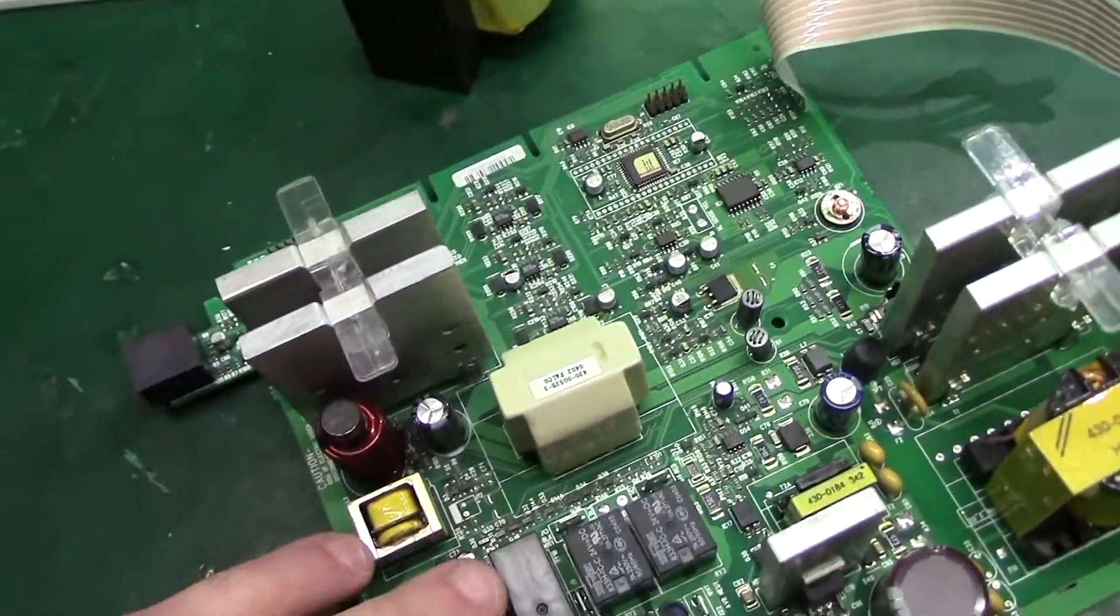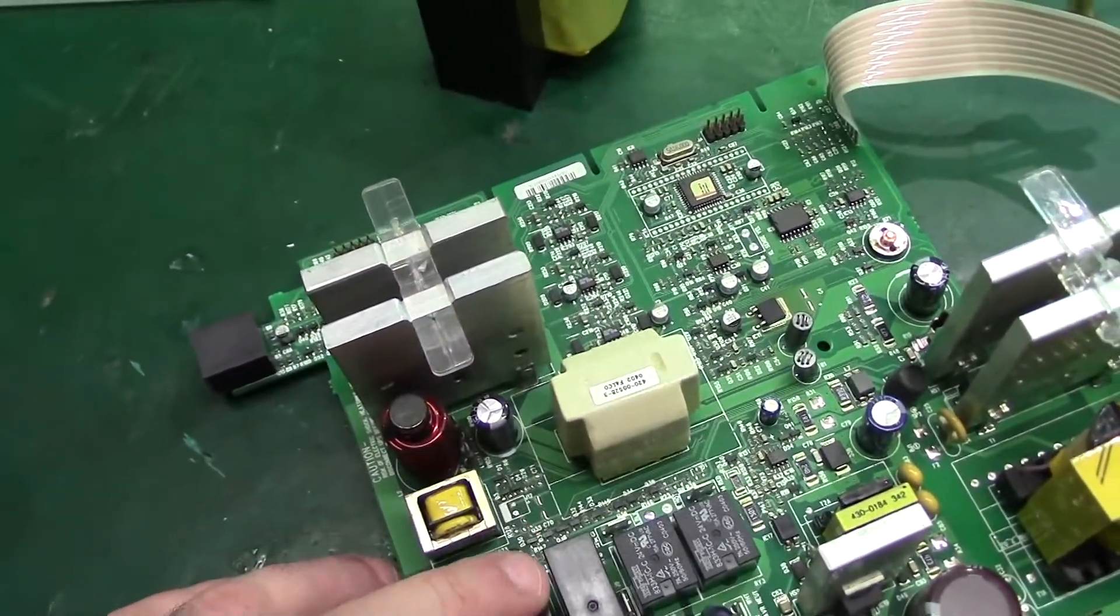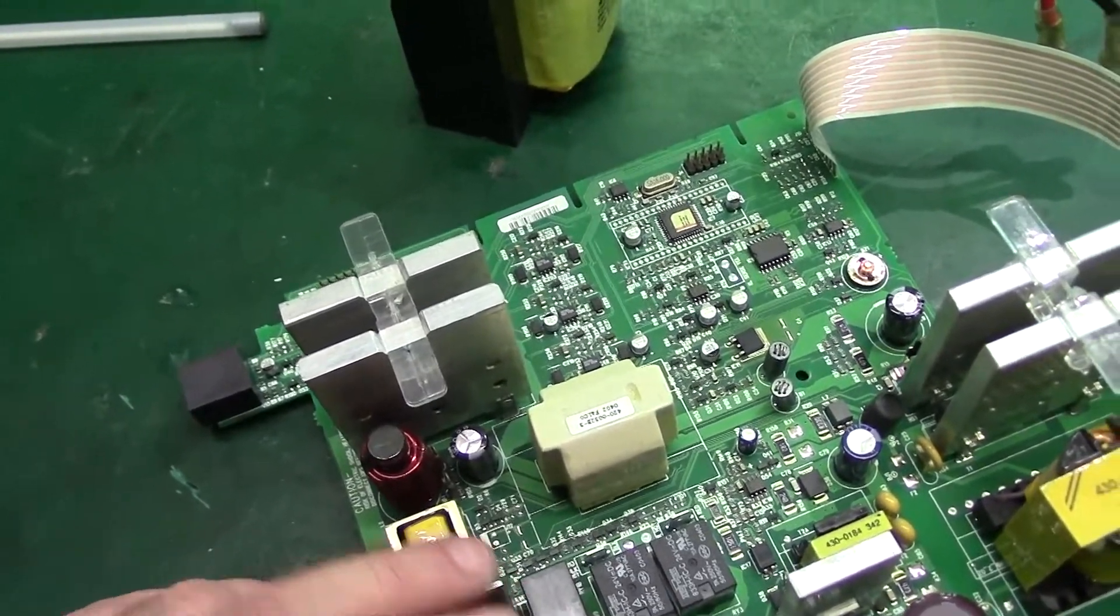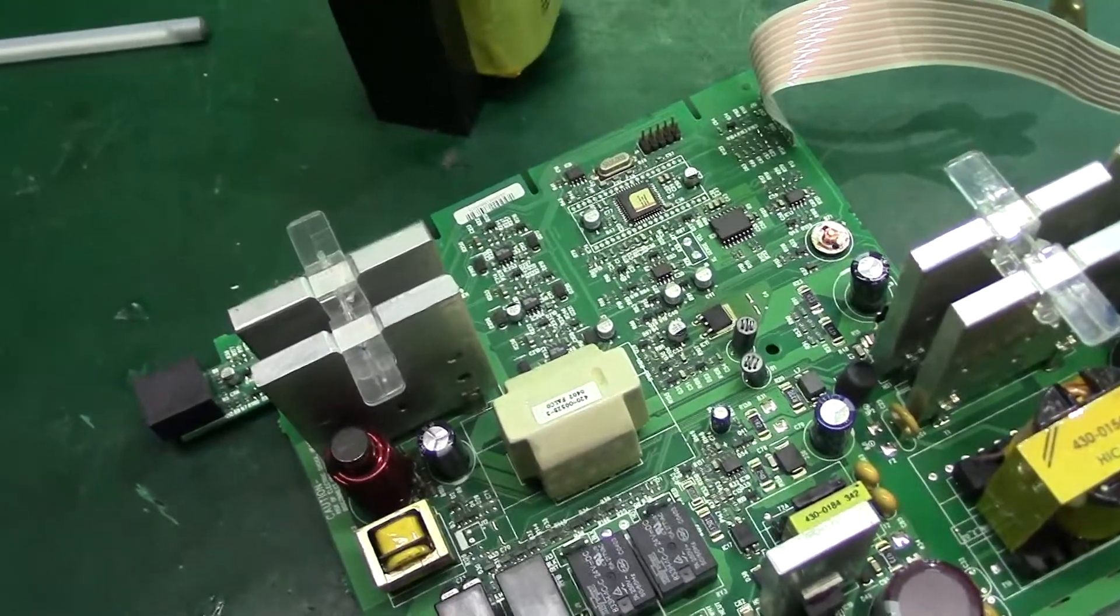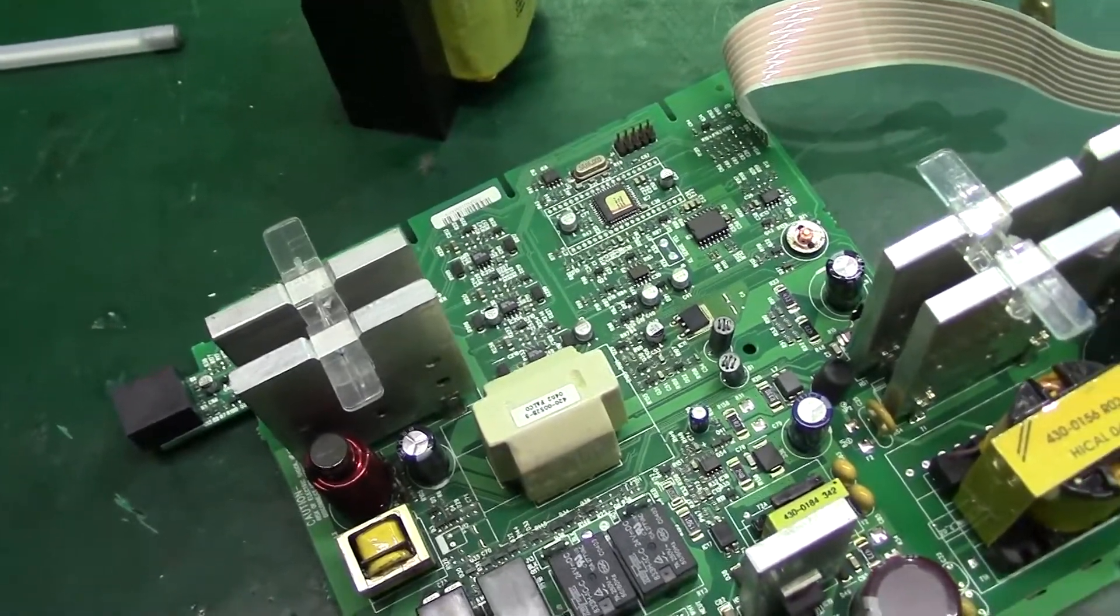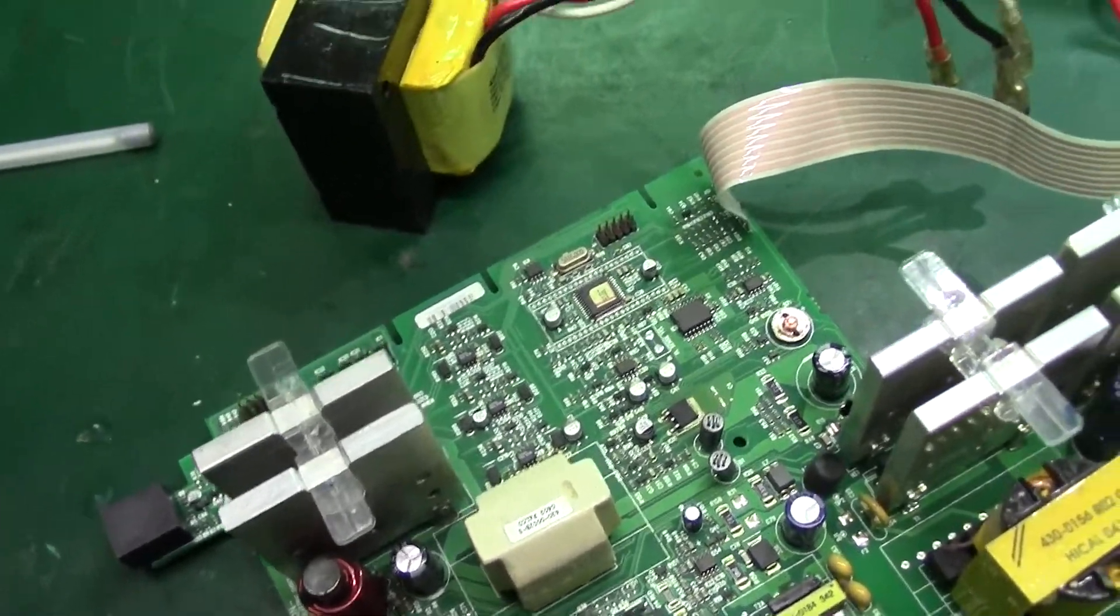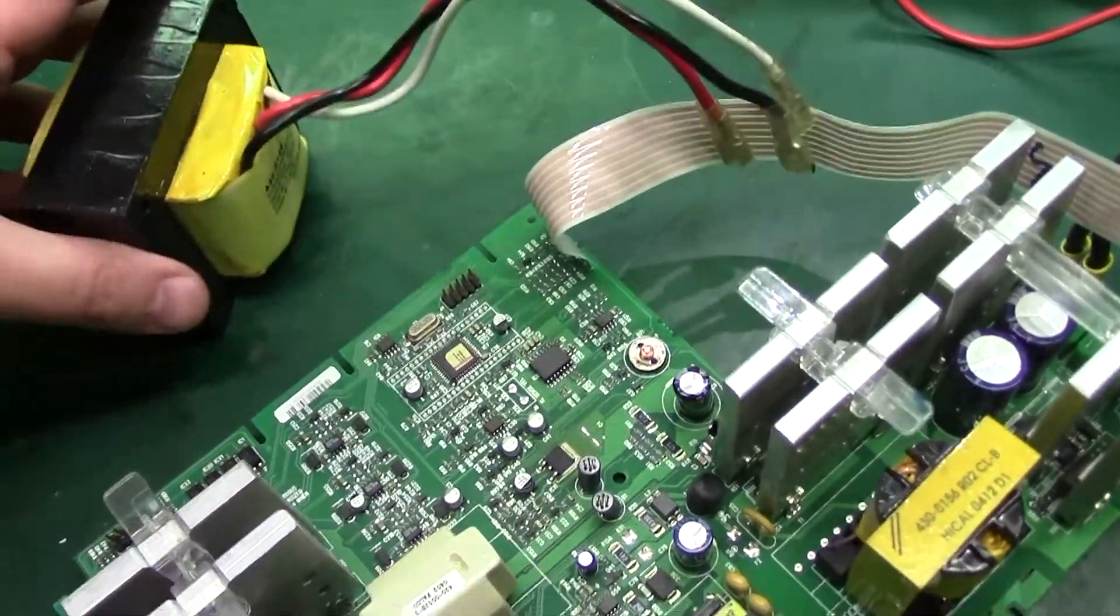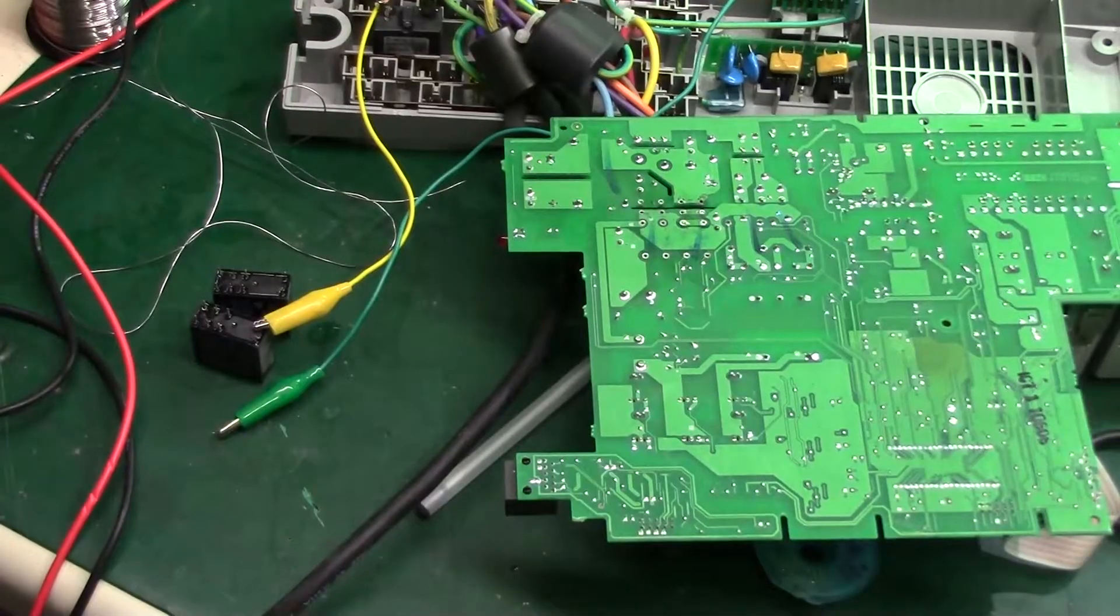Now this one only has a boost feature, but the better UPSs actually have a trim feature, where if the line voltage is too high, they'll actually run through different windings in the transformer and actually lower the voltage level. This one just has like a very basic transformer. So this one can only boost.